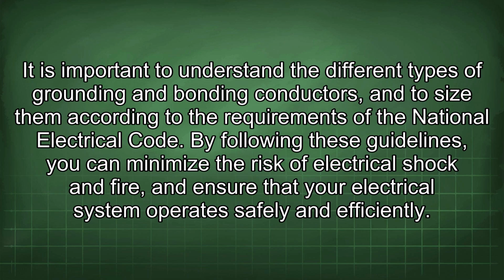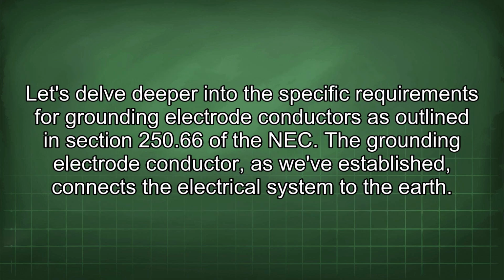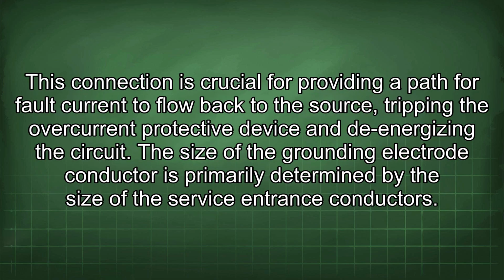By following these guidelines, you can minimize the risk of electrical shock and fire and ensure that your electrical system operates safely and efficiently. Let's delve deeper into the specific requirements for grounding electrode conductors as outlined in section 250.66 of the NEC. The grounding electrode conductor, as we've established, connects the electrical system to the earth. This connection is crucial for providing a path for fault current to flow back to the source, tripping the overcurrent protective device and de-energizing the circuit.